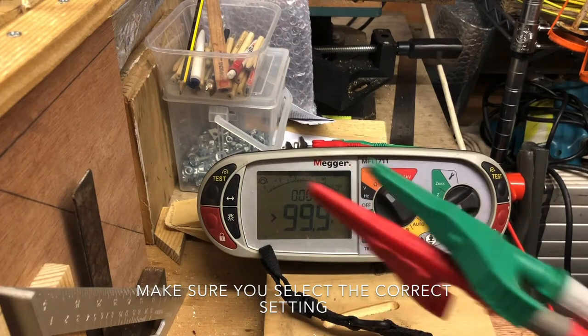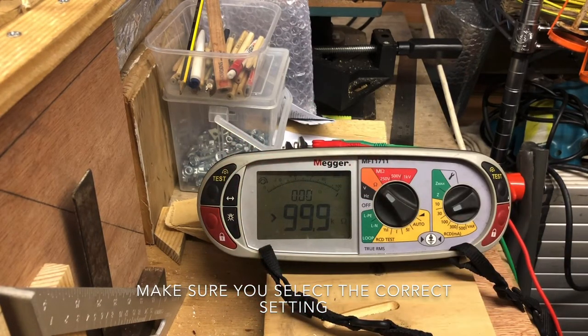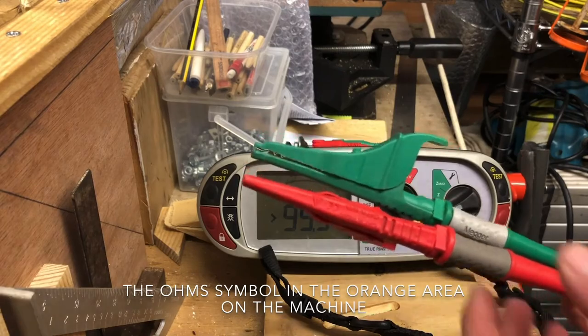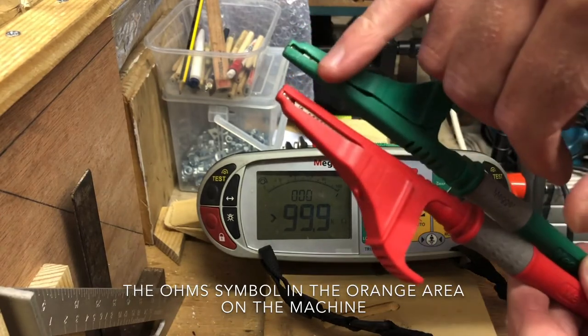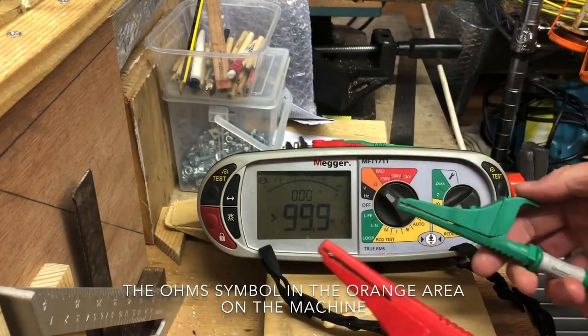Quick demonstration of the MFT1711 from Megger — how to null the leads. I've got a set of Megger leads, and the best way to go about this in all cases is to put the crocodile clips bottom side to bottom side when we come to null the leads.